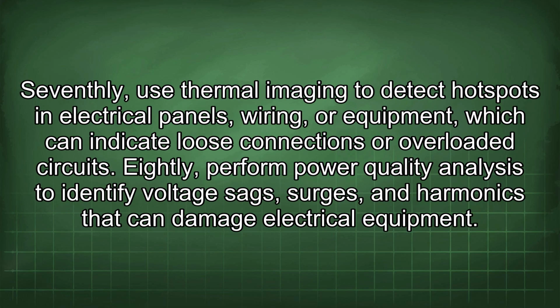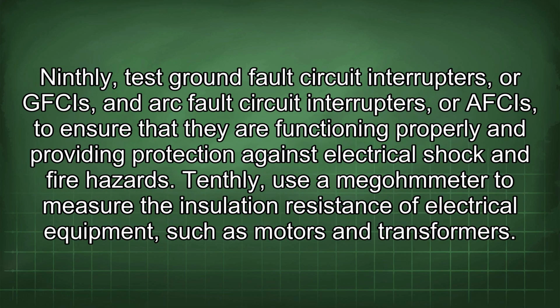problems. Seventhly, use thermal imaging to detect hotspots in electrical panels, wiring, or equipment, which can indicate loose connections or overloaded circuits. Eighthly, perform power quality analysis to identify voltage sags, surges, and harmonics that can damage electrical equipment. Ninthly, test ground fault circuit interrupters, or GFCIs, and arc fault circuit interrupters, or AFCIs, to ensure that they are functioning properly and providing protection against electrical shock and fire hazards.